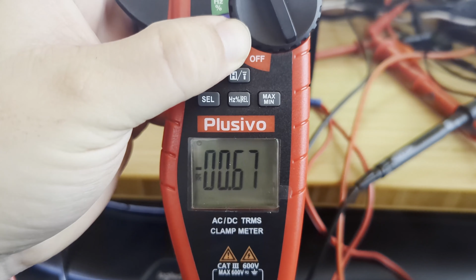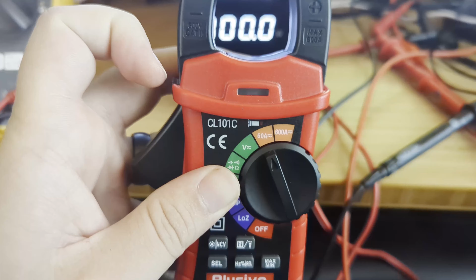And here's another issue with this. Again, we're in amps, 60 amps, and we're reading about negative 0.7. If you turn on the light, so you have to hold the H light here, as you'll see, it's now at 4 amps. There's the light, 4 amps, turn it off, back down to negative 0.8, no light. So as you can see, all the wiring for the light is up here in this general area and causes it to malfunction. So understand that your readings will be pretty bad.